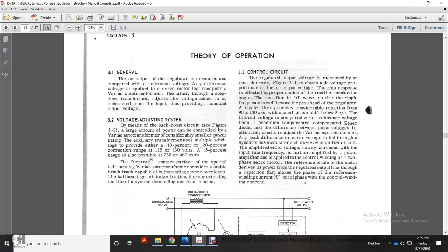The auxiliary transformer and multiple windings should provide either plus or minus 10%, plus or minus 20% correction range at 115 to 230 volts, plus or minus 5% range also possible with a 230 and 460 volt. The Duratrak constant surface of special ball bearing Variac autotransformer provides brush track capable of withstanding severe overloads. Ball bearings minimize the friction and thereby extend the life of the system during continual motion.